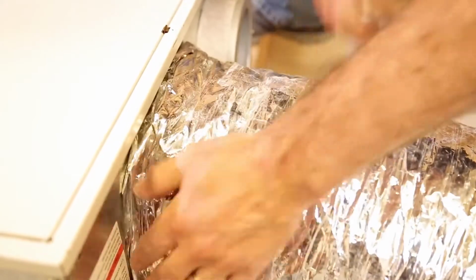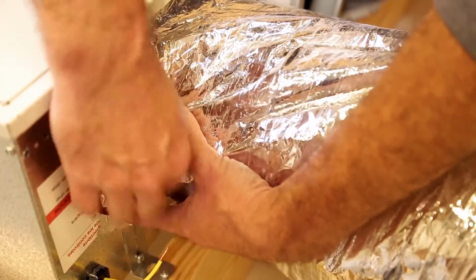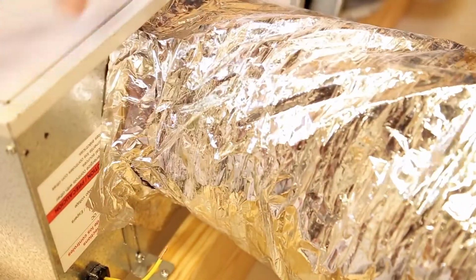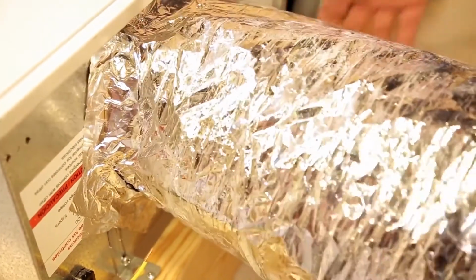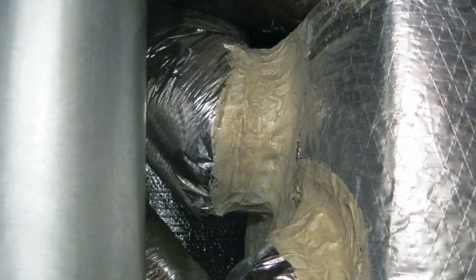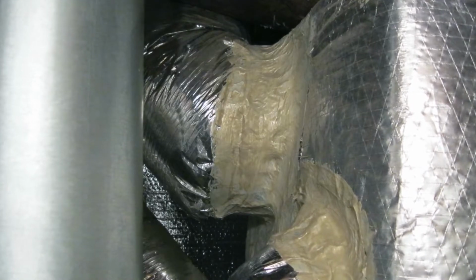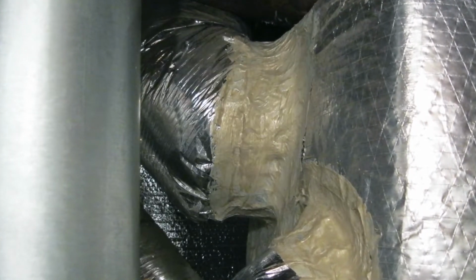Be careful not to tear the vapor barrier. Apply foil tape to the joint, making an airtight seal. Avoid compressing the insulation when pulling the tape tightly around the joint. If using sealing mastic over the foil tape for additional sealing, be sure to use water-based mastic.